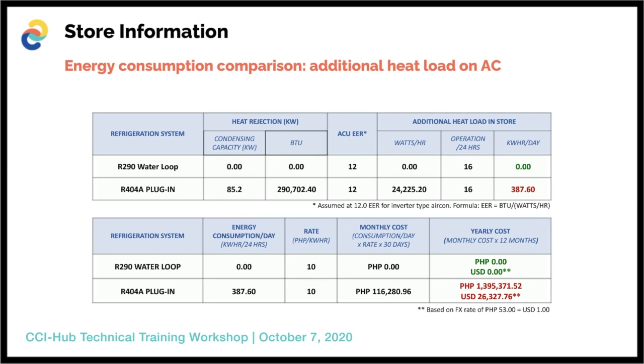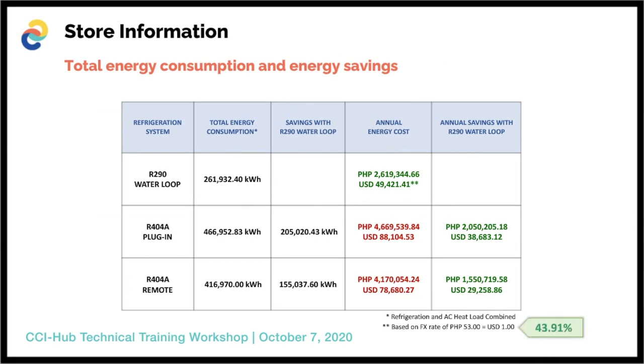And then finally, these R290 water loop systems are not only very efficient, they also have inverter systems in them for the dry cooler, the pumps, as well as the plug-in AHT R290 systems. Because of the efficient nature of these systems, this is a slide that was also presented in Atmosphere. These are calculated numbers, unfortunately. We're still collecting the actual numbers, but we calculated a savings of approximately 43% energy savings compared to their plug-in systems, and approximately 37% energy savings compared to comparable remote systems.